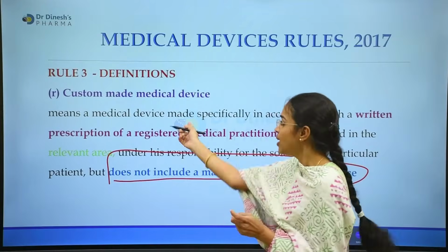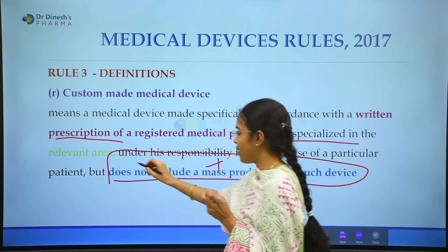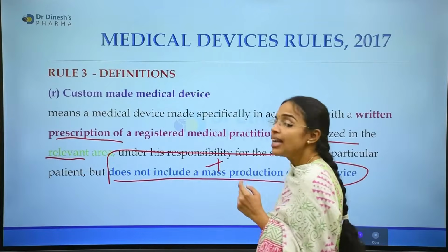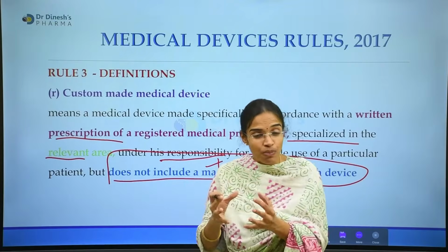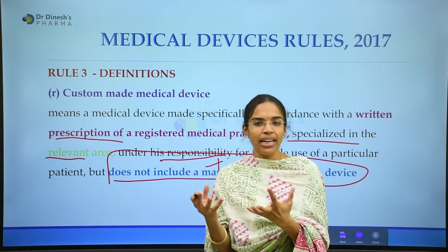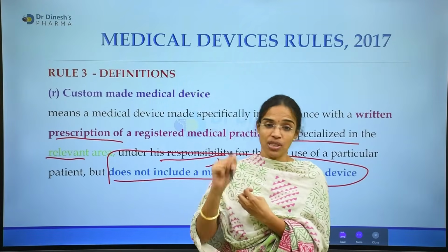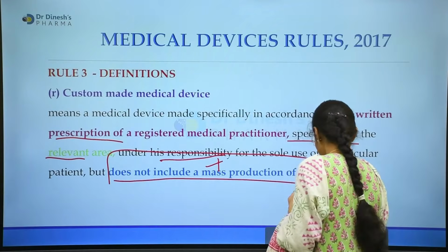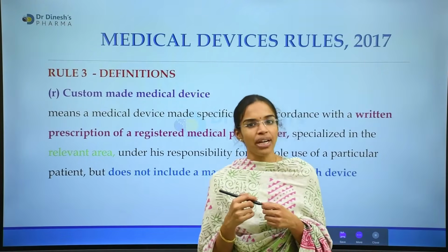It should have these considerations: the prescription of a person specialized in the relevant area, under his responsibility, only under the responsibility of a registered medical practitioner. Okay, not to be made under their own regulations. This MDR specifically mentions this. So this is about a customized or custom made medical device.